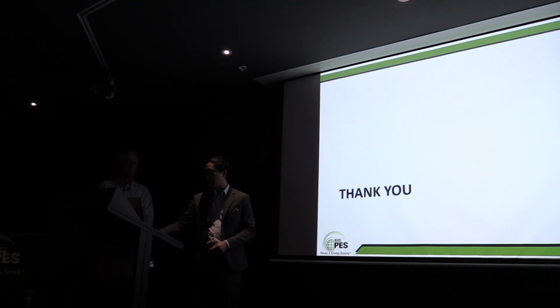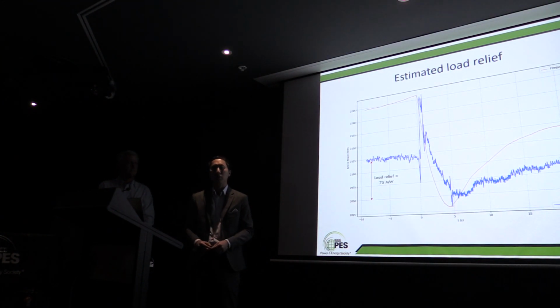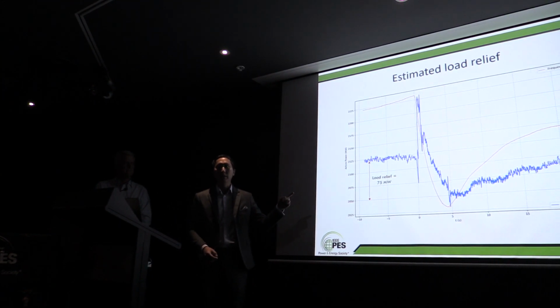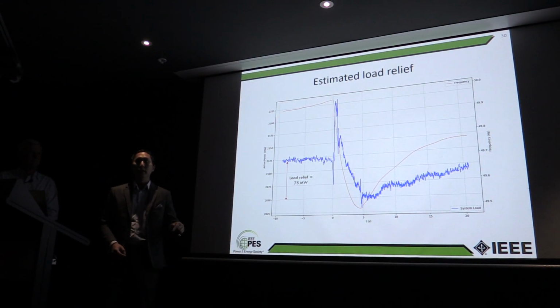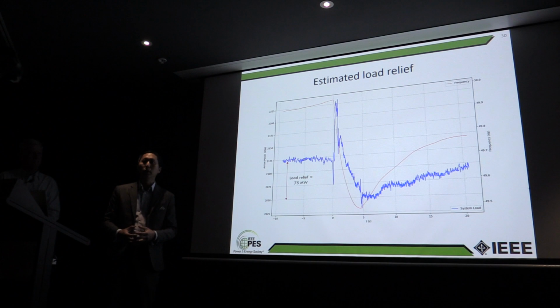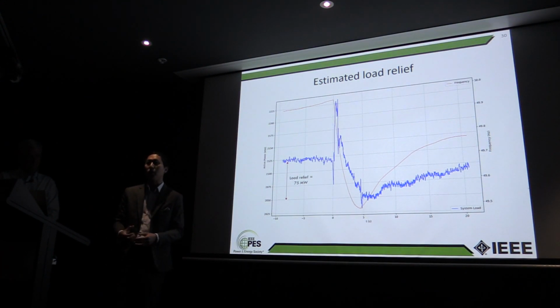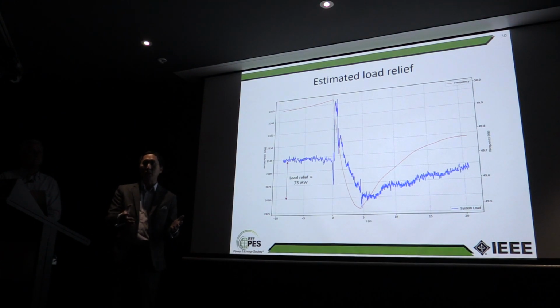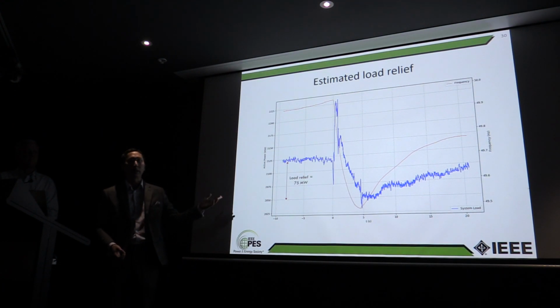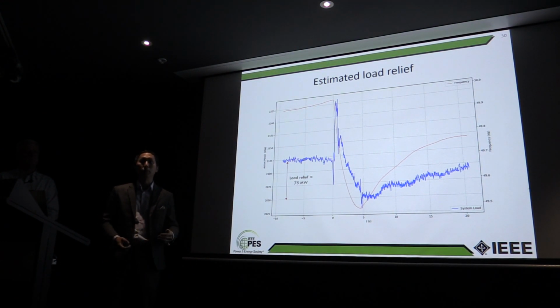Yeah, I mean, we have a thing called load relief, right? I've got some slides here that I didn't mention because it wasn't too relevant. When there is an event and the frequency goes down, there's a tendency for loads to back off as well. That's related to induction machines. As they slow down, they draw less power. But as you say, you have more variable speed drives and power electronic connections in the system, and not just industrial, but at your home with your inverter air conditioners. So we probably expect the amount of load relief in the system to diminish over time. That's something we're looking at anyway and trying to track.